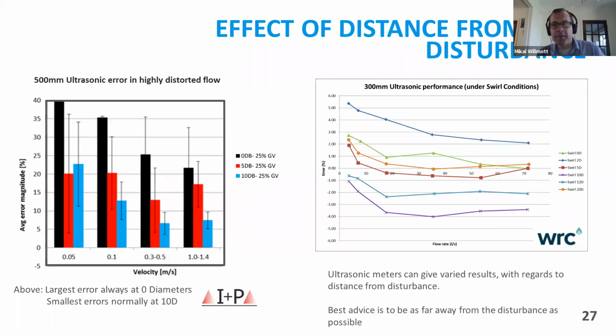Now, this may be a little bit confusing because what we're seeing here is that further away is not always best. And Andy touched on this a little bit earlier, that with ultrasonics, it's a bit more difficult. Sometimes you can be really close to the disturbance and you get a really good result. And sometimes you can be far away, you cannot get quite as good results. But we're dealing with probabilities here. And so from the test data I've seen and from my experience, I would still recommend that you get your ultrasonic as far away as you can from the disturbance.